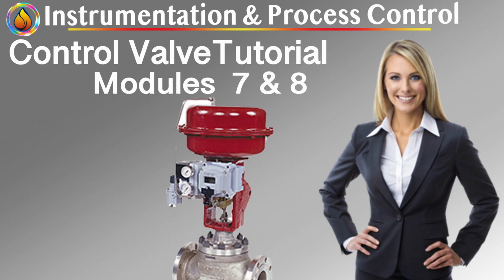Valve-induced oscillations. Many oscillations blamed on controllers originate in the valve. Common valve-driven mechanisms: stick-slip motion, gain changes with travel, directional hysteresis, positioner over-amplification. These oscillations persist even with conservative tuning because the root cause is mechanical, not algorithmic. Performance metrics engineers should track. To manage valves effectively, engineers must track performance, not just availability. Critical metrics: deadband percentage, hysteresis width, T63 response time, small signal gain, valve travel distribution, and time spent near seat or full open. These metrics reveal whether a valve is controlling, merely moving, or actively degrading loop quality.